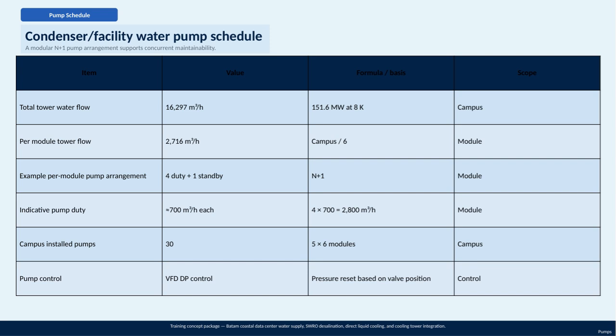Looking at the numbers, the total tower water flow for the entire campus is around 16,297 cubic meters per hour, designed to support a cooling load of 151.6 megawatts with an 8 Kelvin temperature difference. This flow is divided equally among 6 modules, each handling approximately 2,716 cubic meters per hour. Within each module, the pump arrangement includes those 4 duty pumps plus the 1 standby, all typically running at roughly 700 cubic meters per hour.